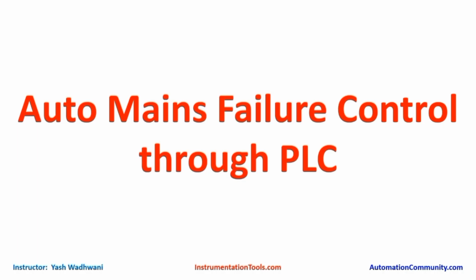Today we are going to see how to make auto mains failure control through PLC. First of all, let me tell you what is the use of this controller. This controller is used to switch on our diesel generator when our main supply through DISCOM is lost.